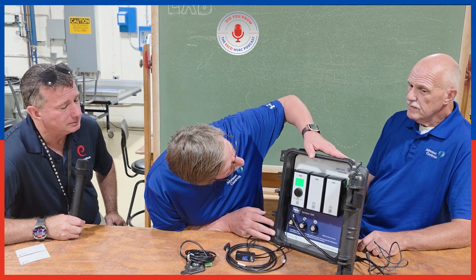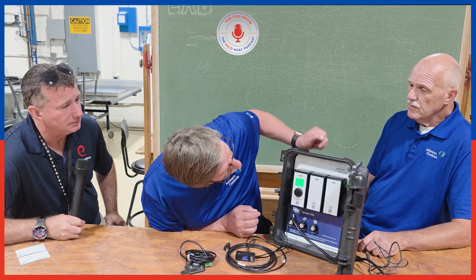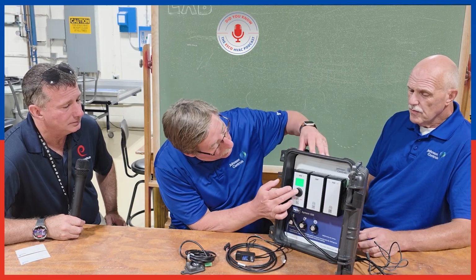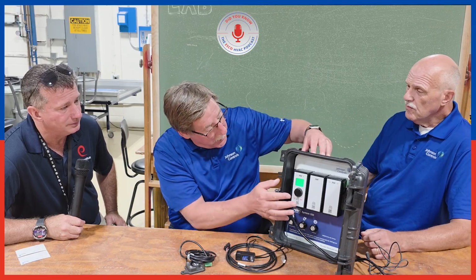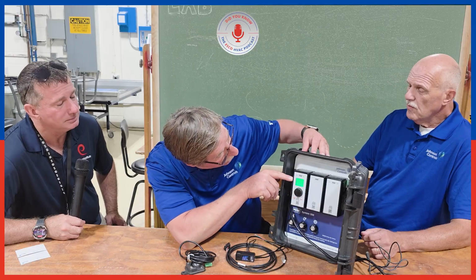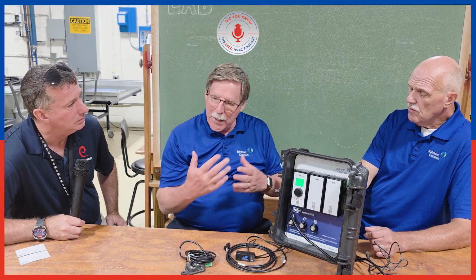Let's see if we're in countdown or not. Looks like we're still in countdown, so we will let it. Oh, okay, we finished countdown now, and now you can see the screen. It's saying confirm that now we can go back into normal mode. And that's, again, because we're connected via Modbus, we can tell why did the controller alert, why did it alarm? We can tell the difference between a refrigerant leak and a sensor failure or a sensor that went end of life. And that's one thing I'm going to talk about now.